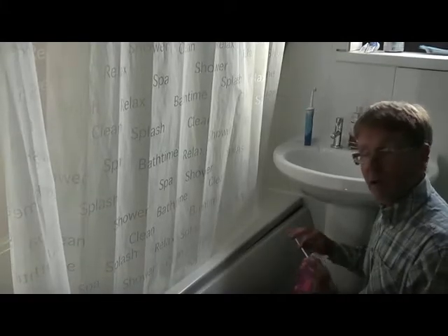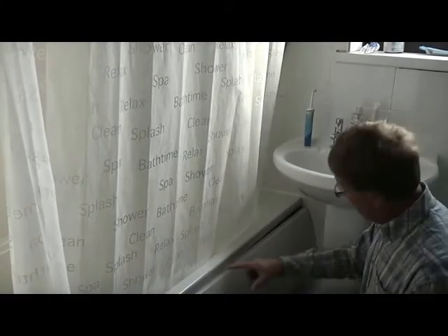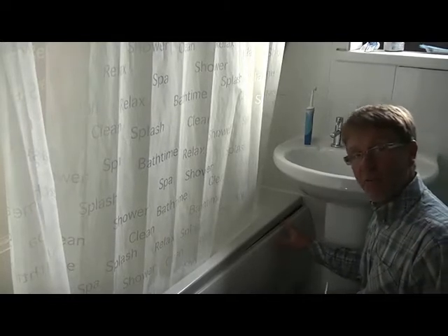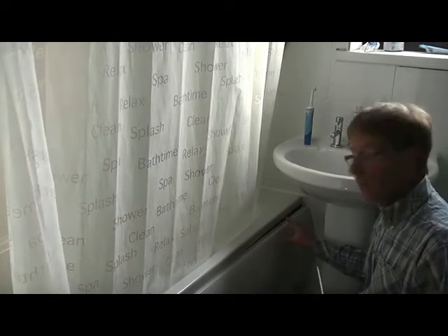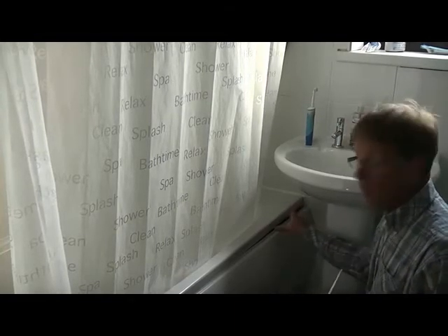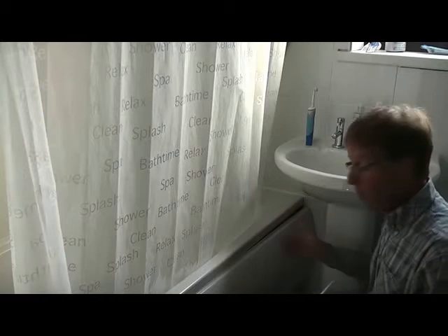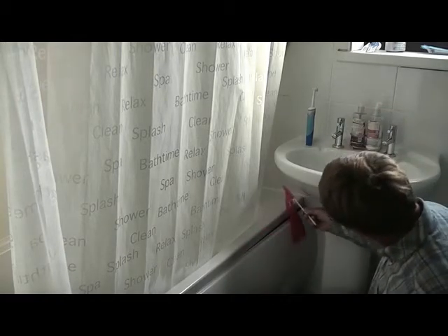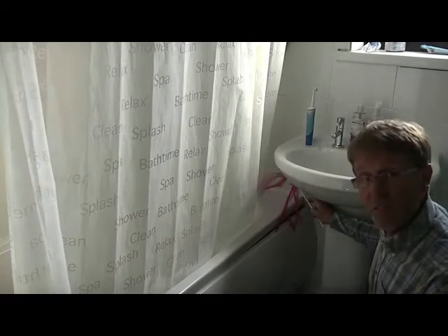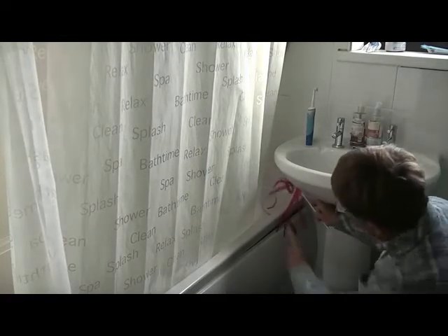So we're into the bathroom now, and immediately what we can see on the bath panel, there is a gap there. Now that gap wasn't there before we started the fan, so what's happening is the fan is drawing air through from a void behind the bath panel, and has actually pulled the bath panel off. So you can see here, look, we've got quite a lot of draft blowing through from here.